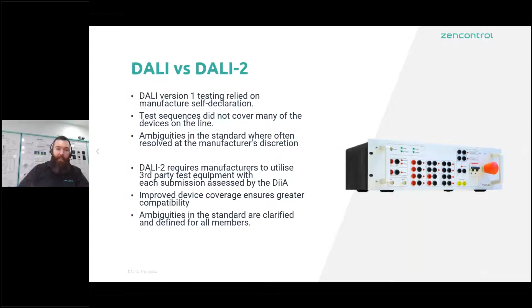Now, a lot of people might say that if we only use DALI 2 drivers, that's going to reduce the scope of devices available to use. But that's simply not true. As of the middle of last year, there are now more currently registered DALI 2 drivers on the DIIA than there ever were DALI 1 products. So the actual pool of possible products you can use in a DALI network is bigger than the DALI 1 network ever was.